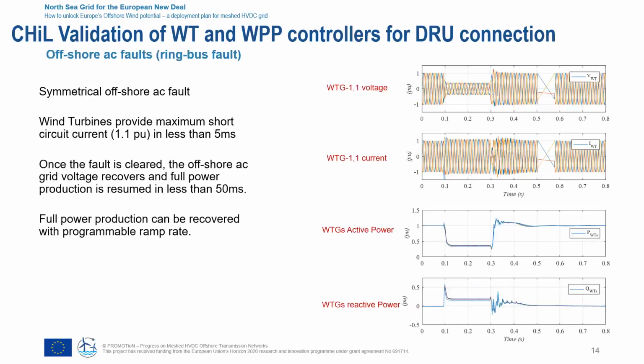The offshore AC voltage is quickly recovered, and active power production is resumed in less than 50 milliseconds. This example shows the operation during faults. In this case, during faults on the offshore AC grid, again we see the top trace is the voltage on one of the wind turbines. The second is the current of that wind turbine, and the other two traces are the active and reactive power out of each one of the individual wind turbines. We see that at t equals 0.1 second, there is a fault, and that fault lasts for about 200 milliseconds.